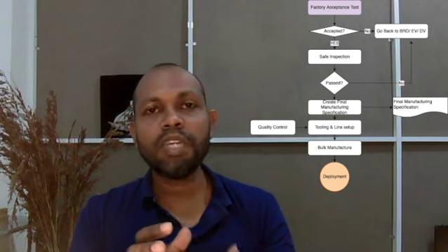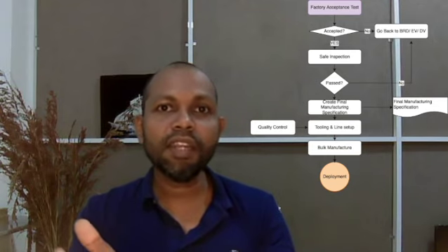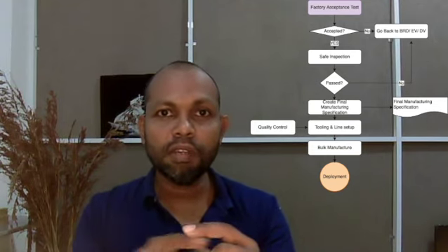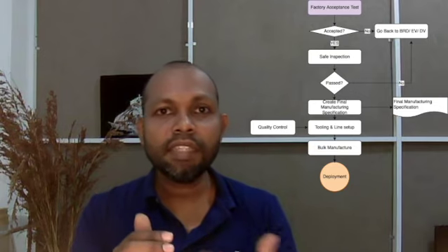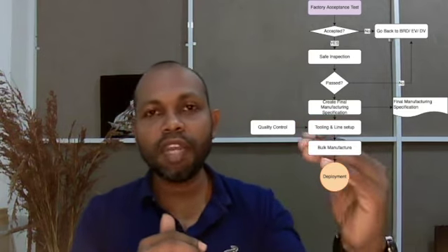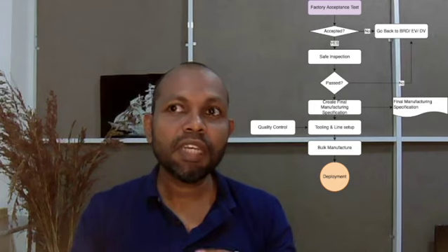So when we submit our application to FDA or MDR, they go through the documents and see that all these steps are verified and validated in the testing documents. That's the most critical document for them. So in the whole process, we start from the business requirement, we design our own internal development, we verify the business requirement and go for the hazard risk analysis and verify that this is safe for the patient, and then start the development process.